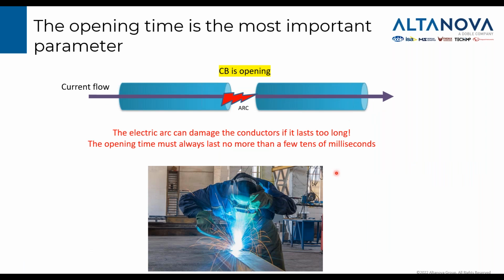The reason why the arc must remain for the shortest possible time is because this arc can damage the surface of the metallic parts. And this arc must remain no more than a few tens of milliseconds. Otherwise, as you can see in the picture, this is the effect that you get.